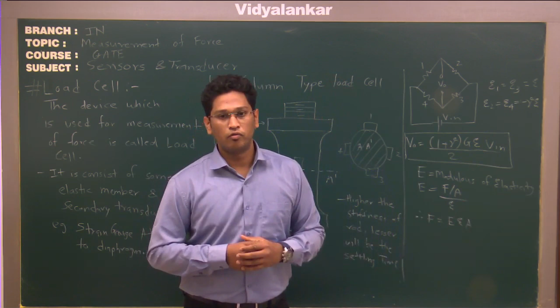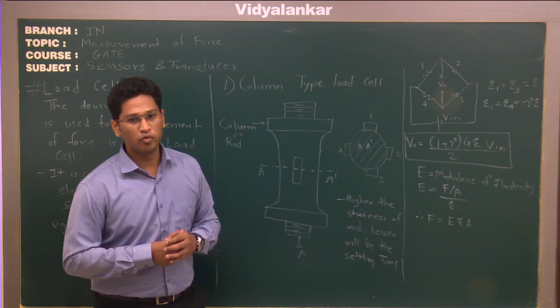Strain will be F upon A divided by E. So using this formula and the modulus of elasticity, you can determine either the force acting on it or the strain acting on it. So depending upon your requirement, you substitute whichever value is to be measured in place of epsilon. If you are provided with the output voltage and the question demands that you determine the force acting on it, then simply measure the output voltage and substitute epsilon equals F upon AE. That will give you the output voltage and force relationship. So this is how you can measure the force which is acting on this column type device. So this is the first type of load cell.